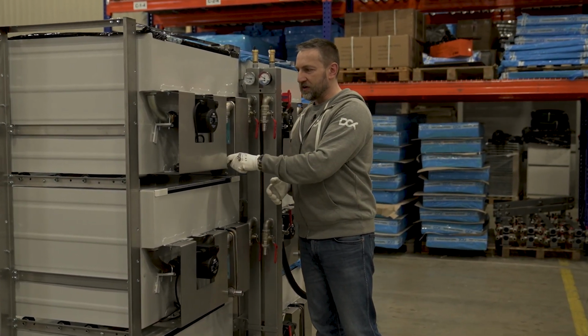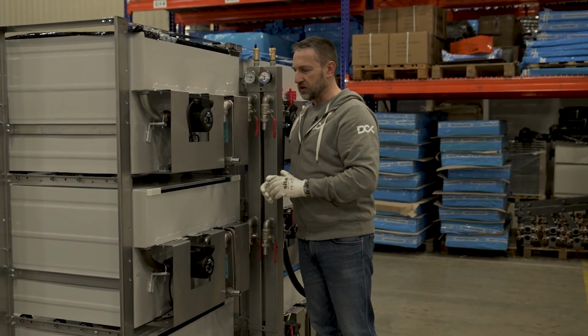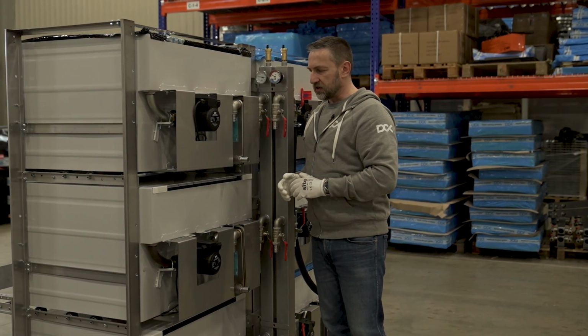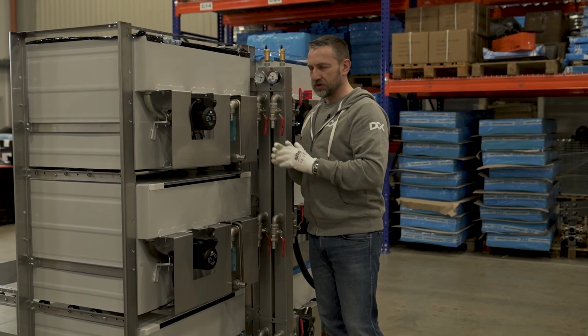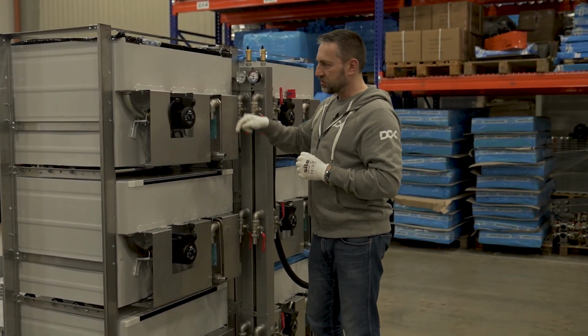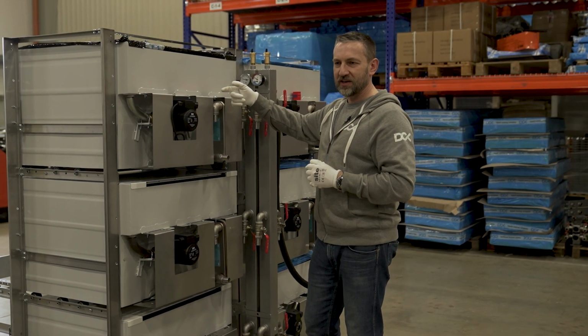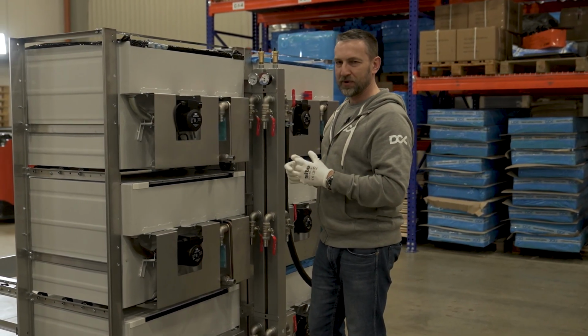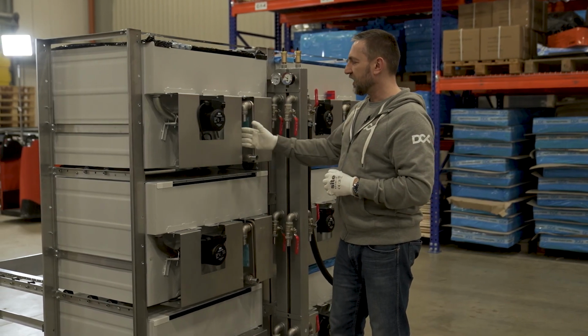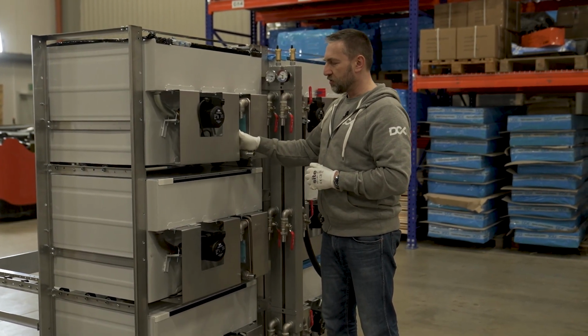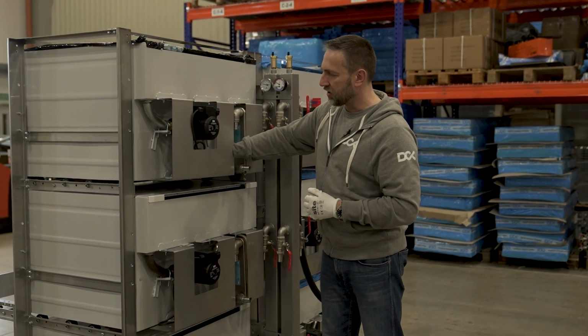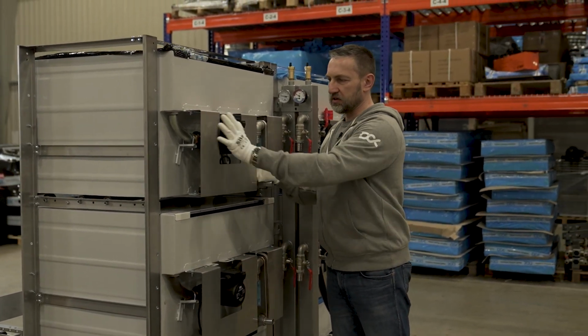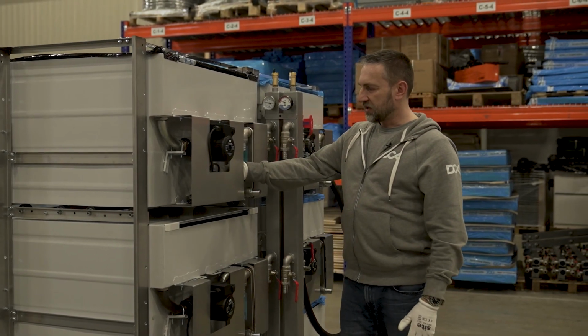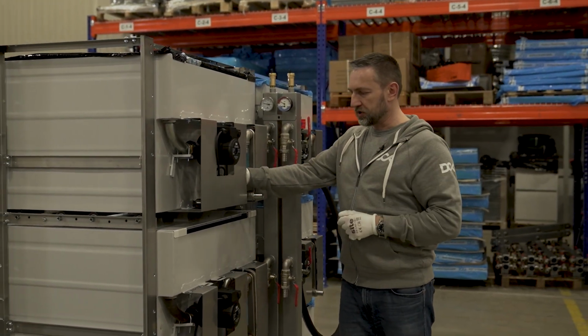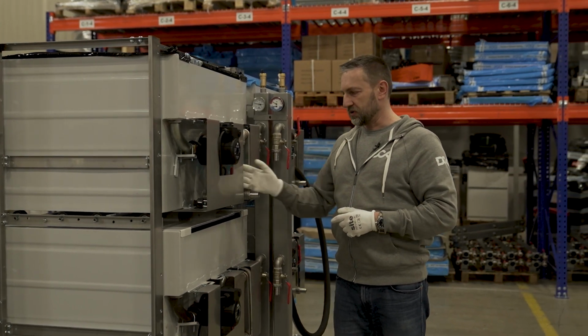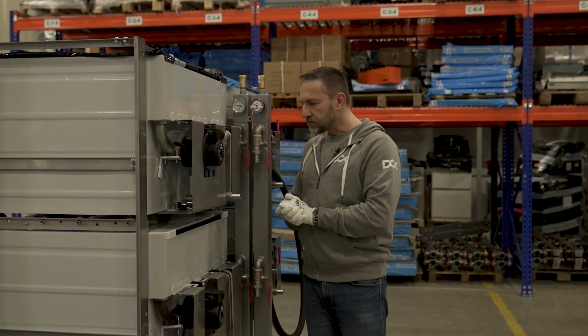So the internal loop is fully closed. You don't need to do anything with that one. There's only one thing you need to do when you're starting the operation. You just need to remove the caps from inside of the enclosure, from the fittings. There are plastic caps on top of the inlet and outlet, and you need to open one valve which is hidden here below the cover, which is a protective cover. There's one valve on the bottom of the enclosure which you need to open, which I will show you in a moment.